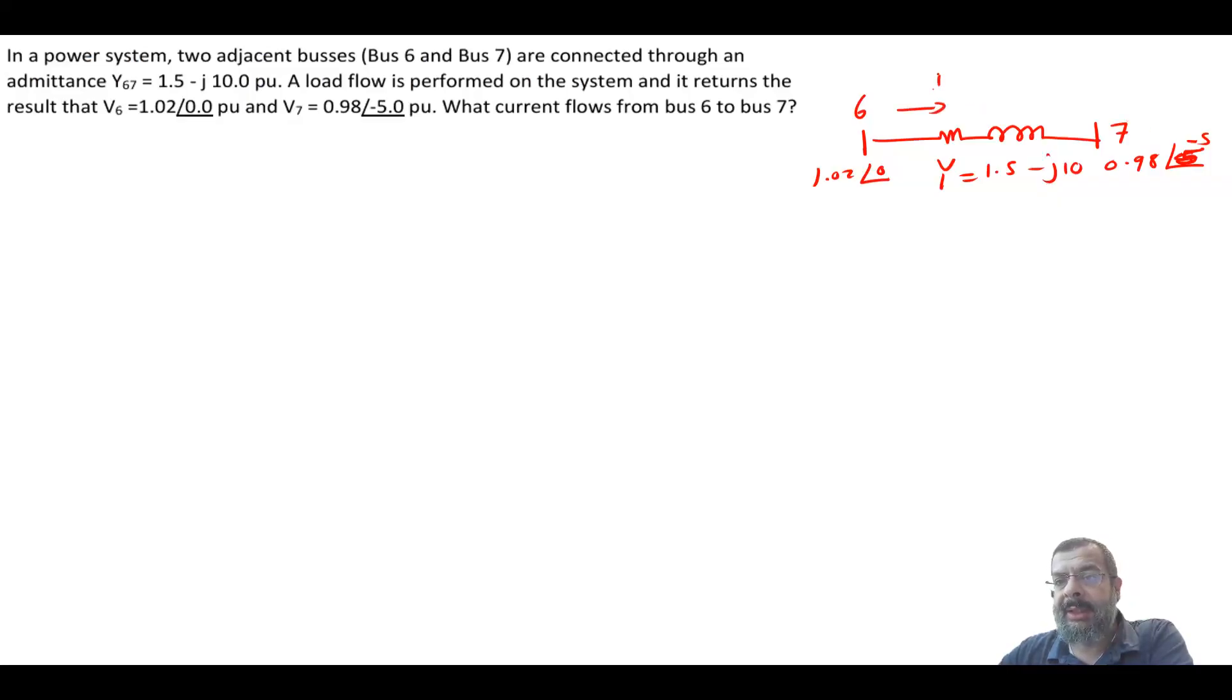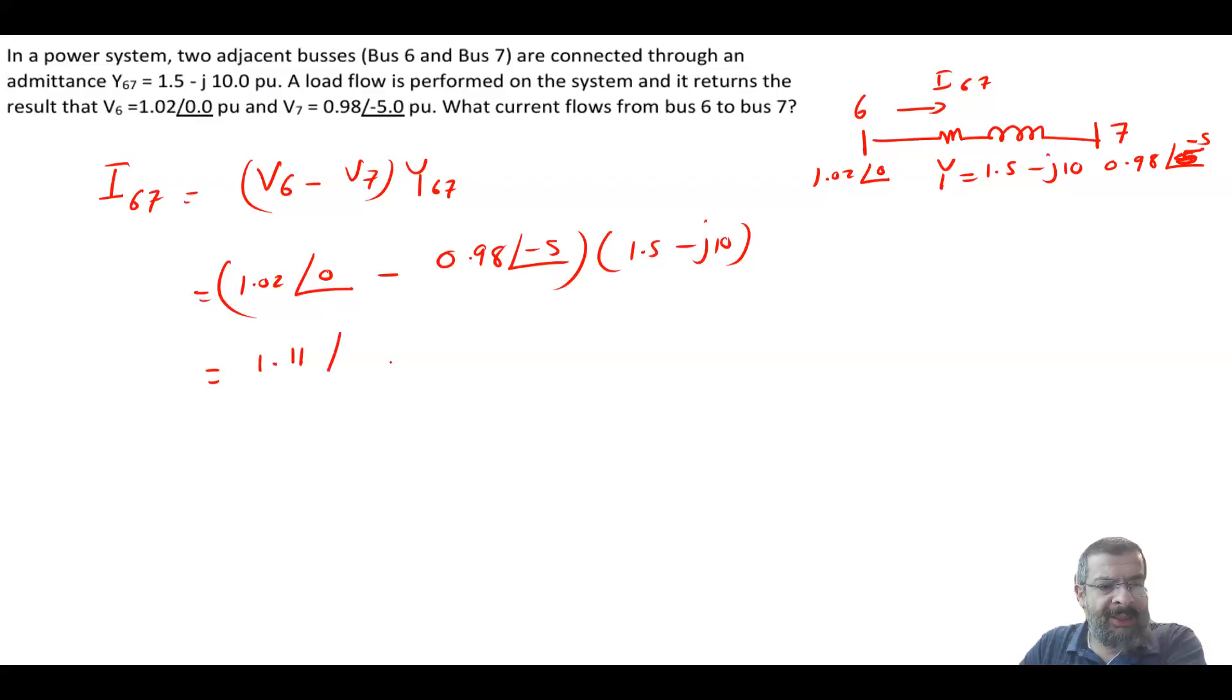Very straightforward problem. So I from 6 to 7 is equal to V6 minus V7 times the admittance from 6 to 7, which is equal to 1.02 angle of 0 minus 0.98 angle of minus 5 times 1.5 minus j10. Everything in per unit. So the current would be 1.11 angle of minus 32.7 per unit. Very easy question.